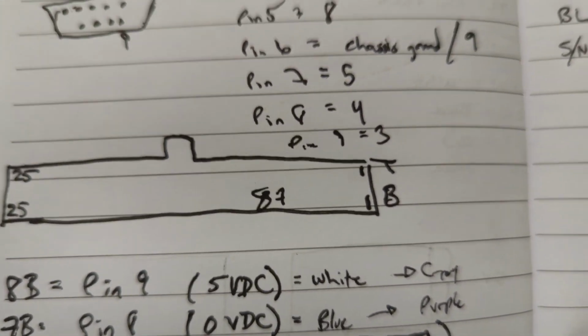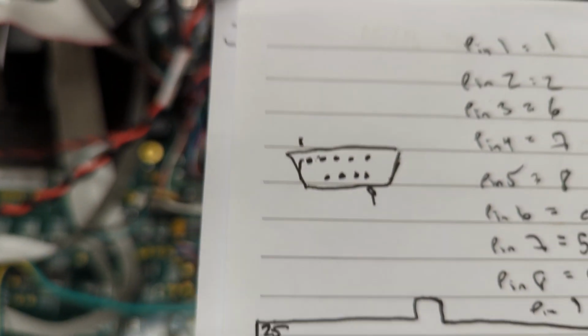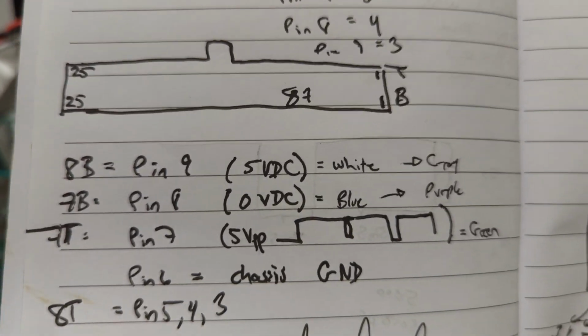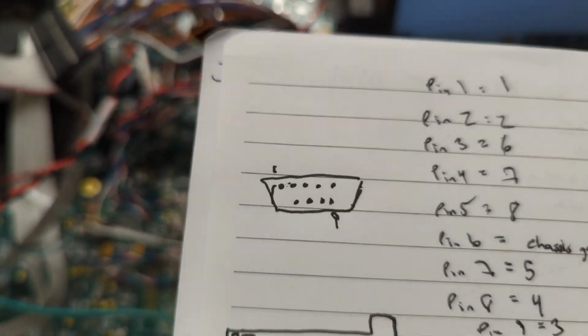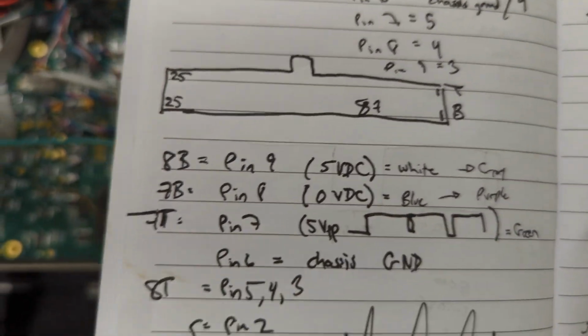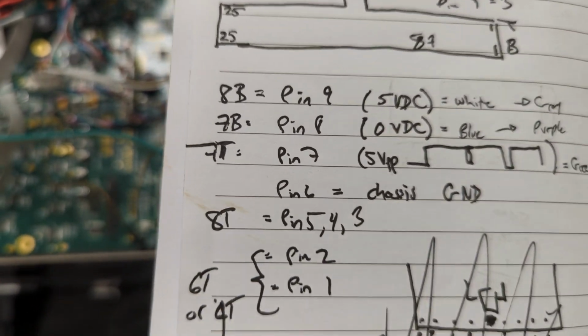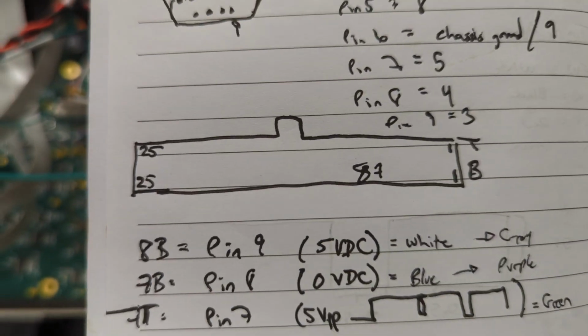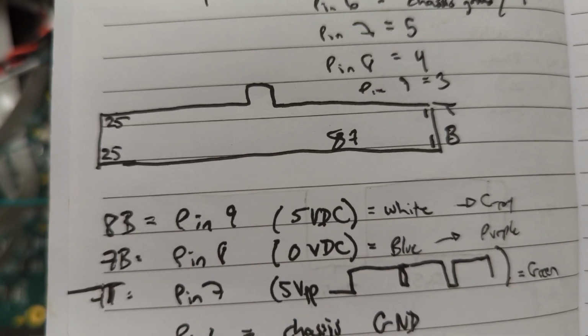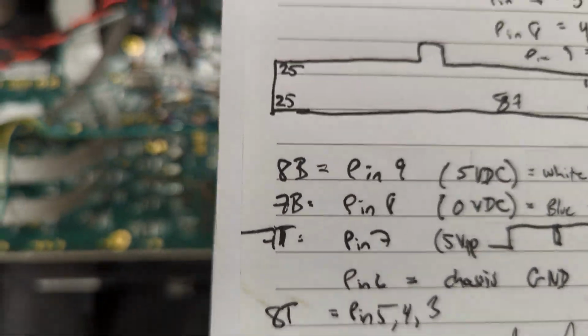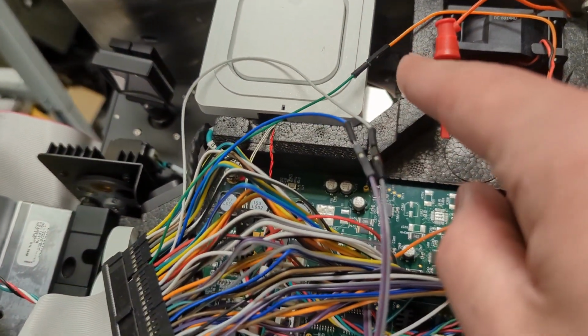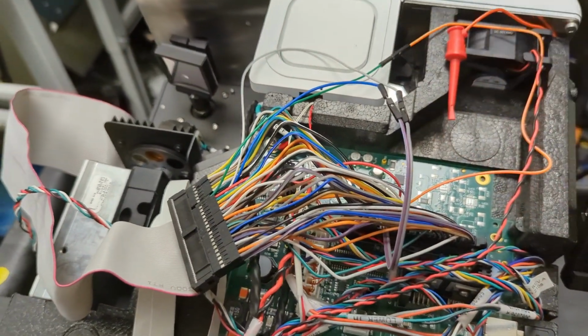So 1 is on the right, 25 is on the left. It's a 50-pin cable. The pin of interest where that pulse is, is 7T, if the top is where that notch is and the bottom is the other side. Okay, so 7T. I actually have, sorry about that, this green cable right here, that is then going on to the orange one. That's the jumper wire that I was disconnecting to then connect it to my pulse generator.